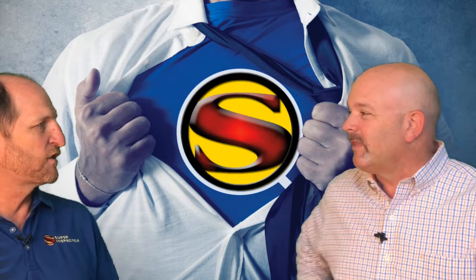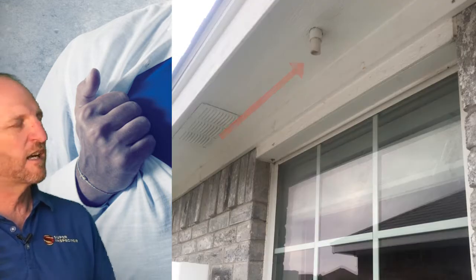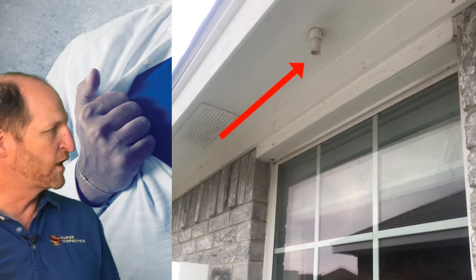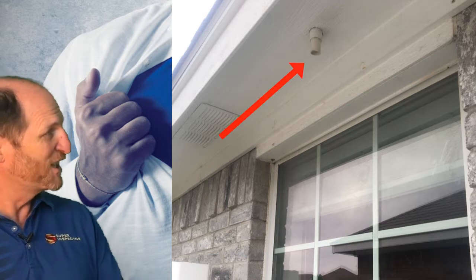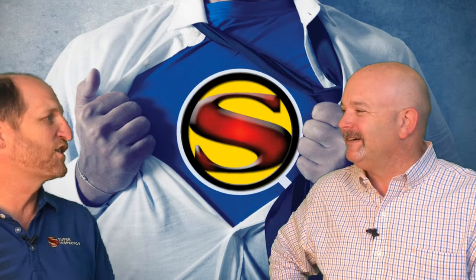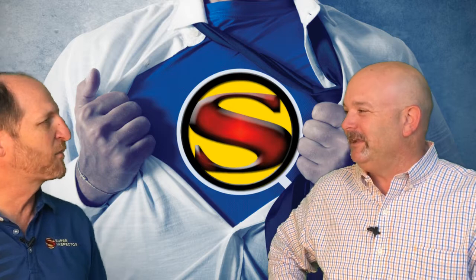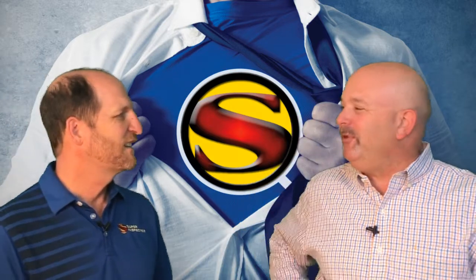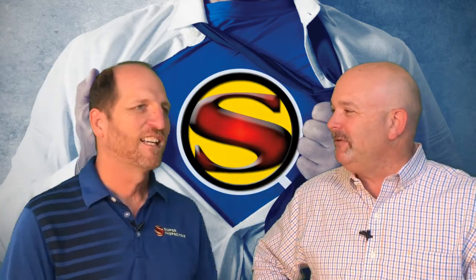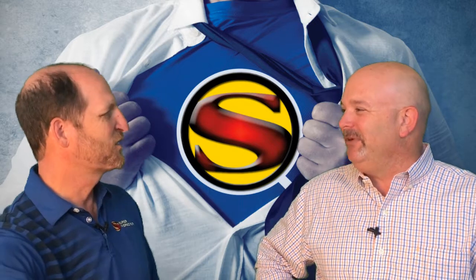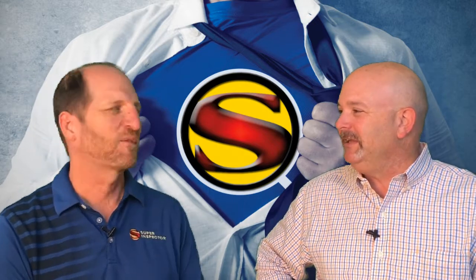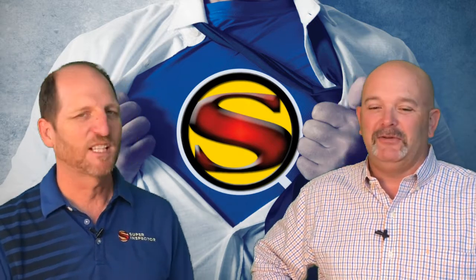Right. So those drains, the secondary drains, are located on the outside of the house over a door or window. Yeah. And they're there for a reason so that you'll see the drainage and know that there's a problem with the primary drain. Because I've heard people say, why would they put that pipe there? Right. And then they reroute it somewhere else. Yeah, they put it somewhere else and then they never see it again. Right. Yeah, so that's very interesting.